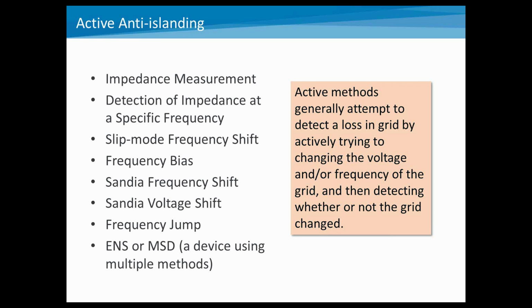So typically these work best if you have a very stiff grid. That means the DR in relationship to the size of the grid is relatively small, and the DR will not be able to move voltage or frequency around. But active anti-islanding techniques in general are trying to create a disturbance. When it moves into an islanded mode, it's actually able to move voltage and frequency, and then typically will push faster until it pushes outside those trip windows.